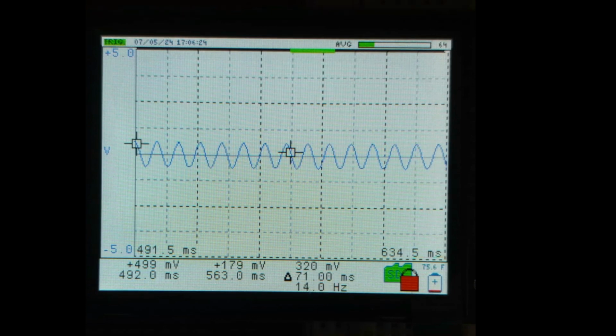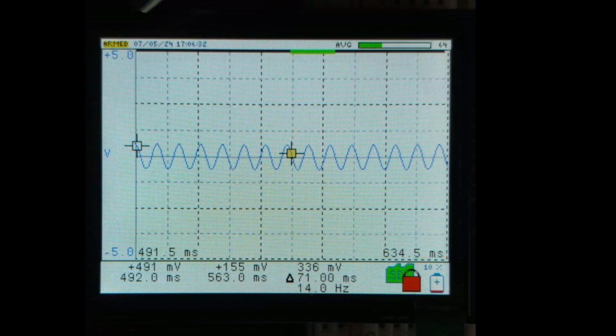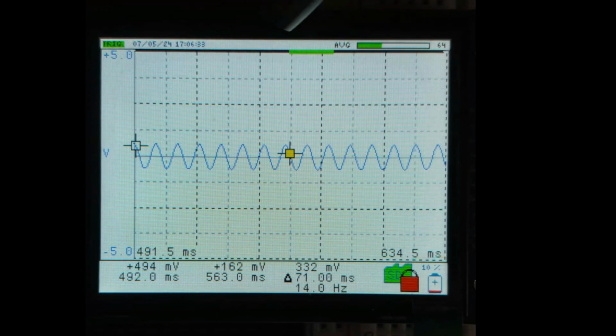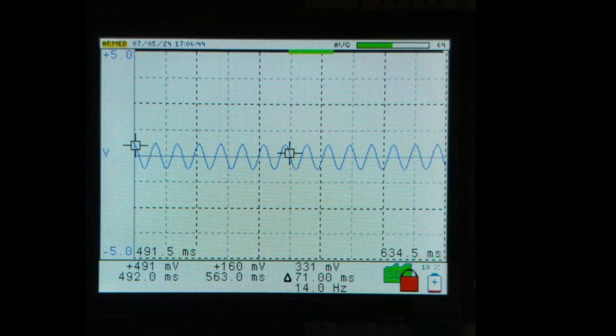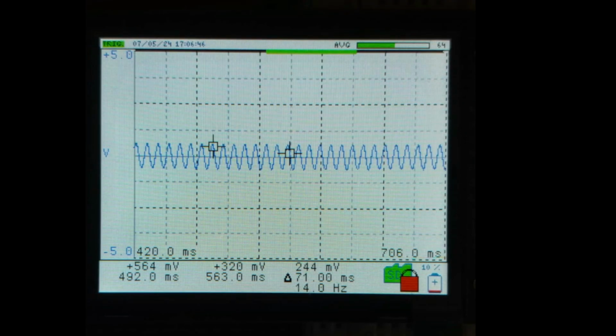So here's the maximum zoom in. There's a little bar graph at the top here, that little green out of that big black line that shows you what percentage of the waveform you're really zoomed in to look at. And when you zoom in, it zooms in centered about the active cursor. So you'll see the active cursor in the center of the display. Of course, you can zoom back out again.